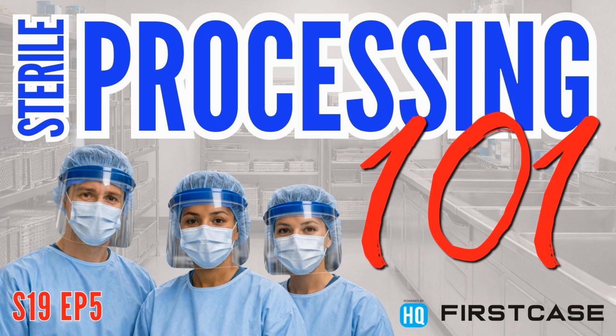So we want cool and dry surgical instruments for storage, but the steam sterilization process is very hot and very wet. So at the end of that 4 minutes, the sterilizer will start a drying phase, which is going to try to hold those instruments in that sterile state that we just accomplished in those 4 minutes, but dry all of the water out of the tray so that whenever you open the sterilizer, what comes out are really hot but really dry instruments. That drying phase typically lasts around 30 minutes, sometimes 40. Again, just have to follow the IFU.